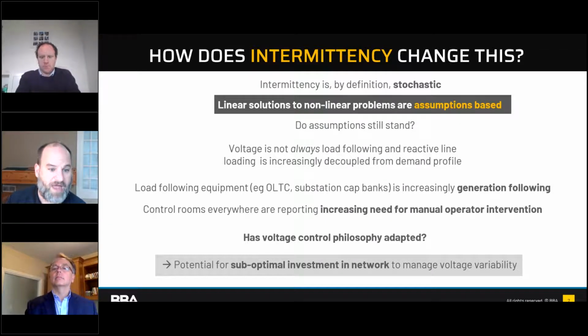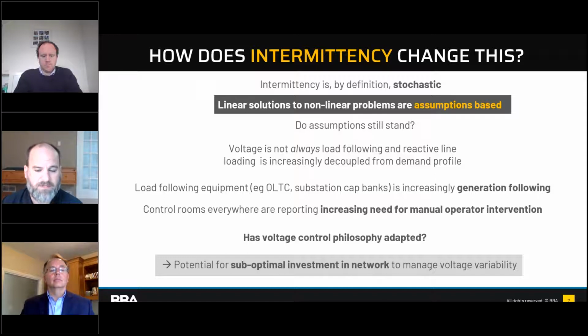But all of a sudden, what the randomness of intermittency does is that, guess what? Sometimes voltage is no longer load following. Sometimes it's the reactive line loading that's determining the voltage, and that's a factor of flow, a factor of randomness. And like I say, we know that this is happening.